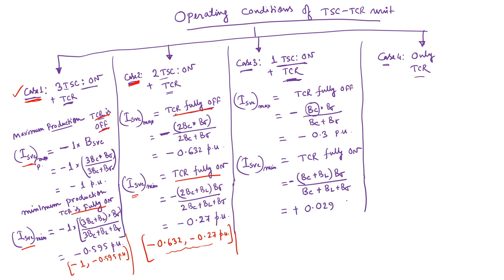0.029 positive per unit. Now, when this I SVC current drawn by this SVC comes out positive, then according to our convention it is a kind of inductive operation, so it is basically absorbing VAR. So therefore for this particular case, that is case 3, when only one TSC will be operational and the TCR will be turned on...